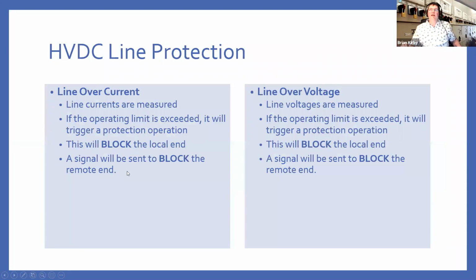If we now look at line protection, the two base protections for an HVDC line are overcurrent and overvoltage. Because what happens on the line is totally controlled by the power electronics, if we detect a current or voltage fault, we can just block locally and send a signal to tell the remote end to block, and we can remove the current flowing in the line, but we don't have to shut down the converter stations themselves.